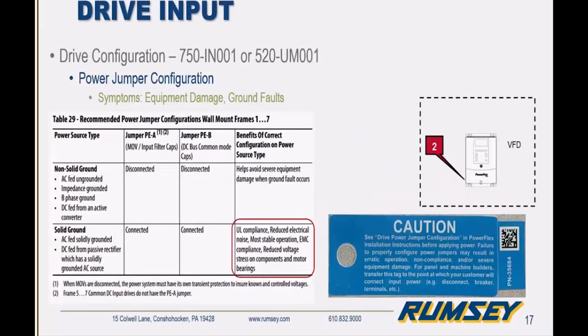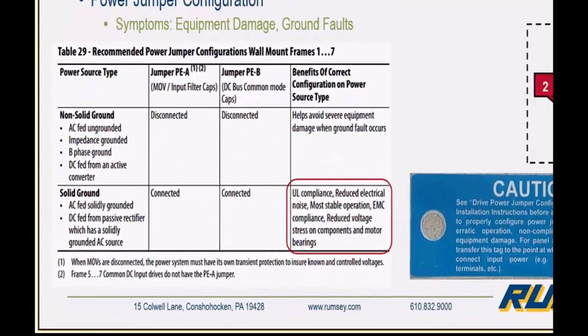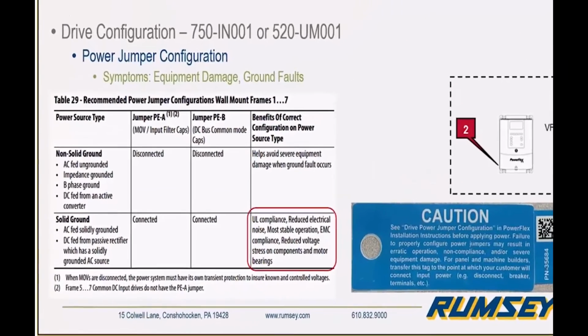So in addition to making sure we have the proper grounding, we also want to make sure that the drive itself is configured correctly to operate on the system that it is being installed in. So on the left-hand side here, there is a table that is from the PowerFlex 750 series installation manual. It actually shows a chart that on the left-hand side lists the power source type, and then the two columns to the right actually show and recommend which position the PE jumpers or power jumpers for the drive need to be installed in according to those power source types.